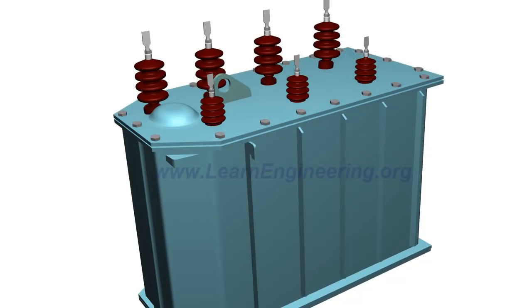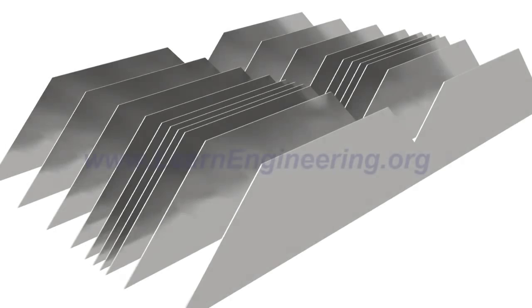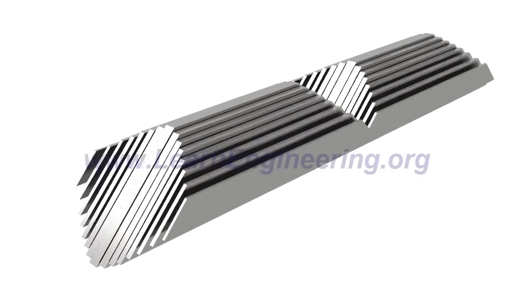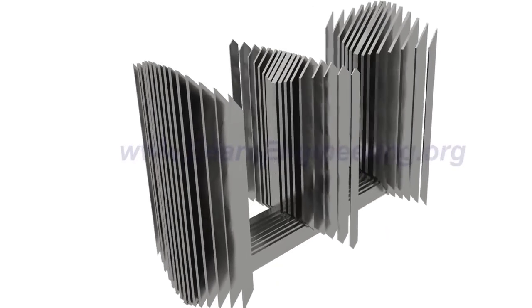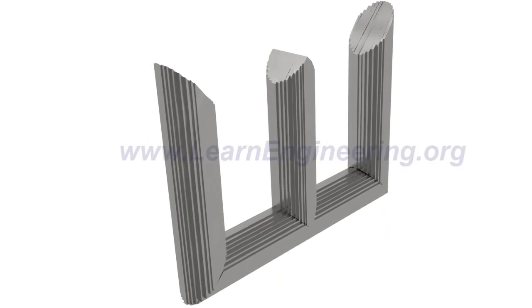The core of the transformer is made of thin, insulated steel laminations. Such steel laminations are stacked together, as shown, to form three-phase limbs. The purpose of thin laminations is to reduce energy loss due to eddy current formation.